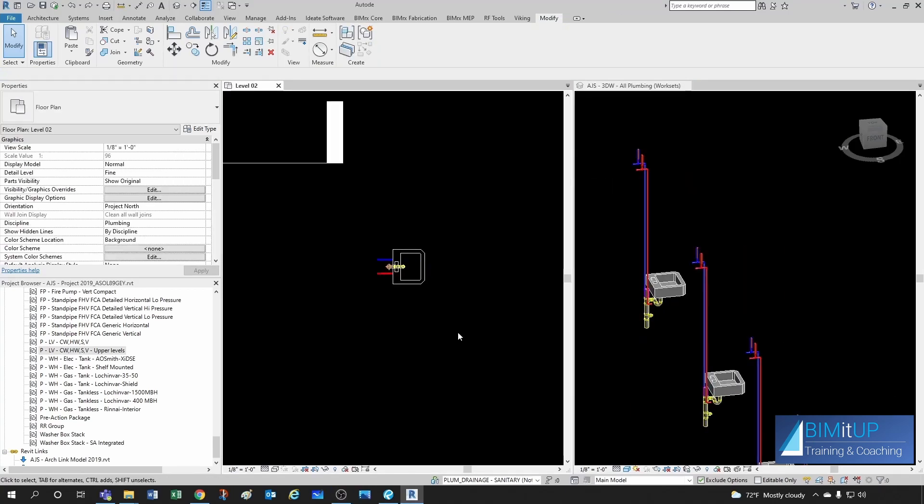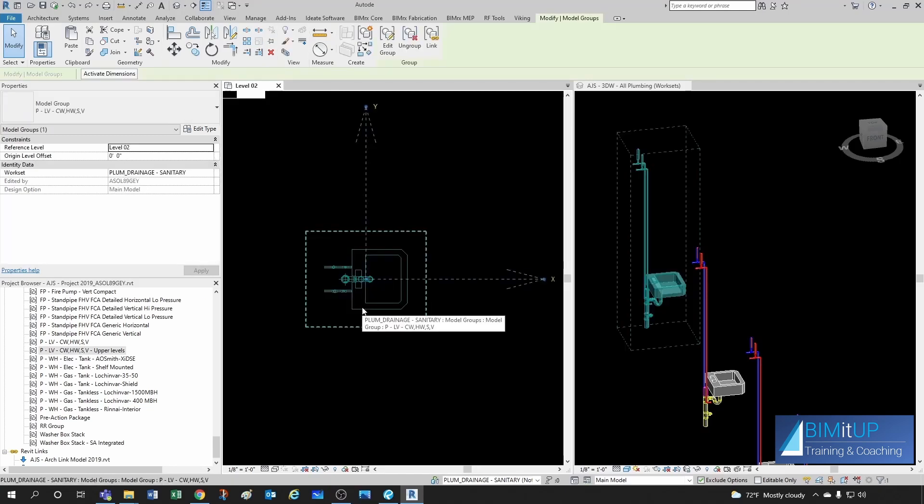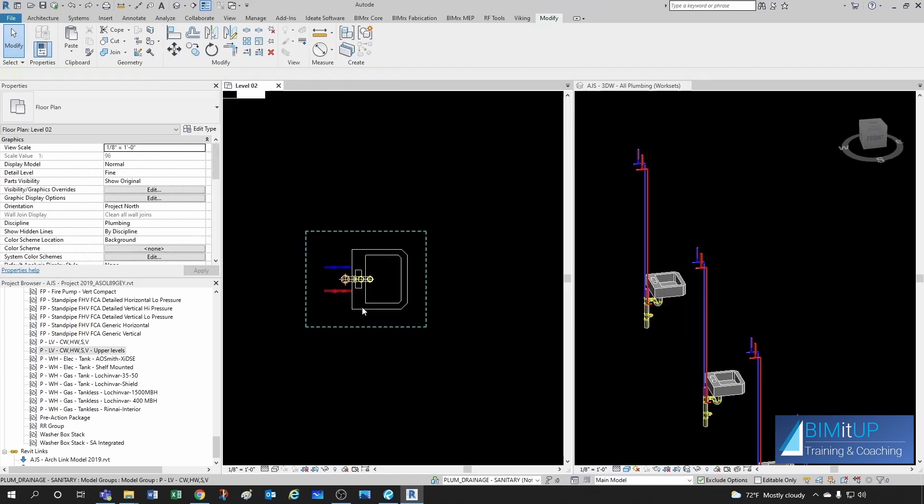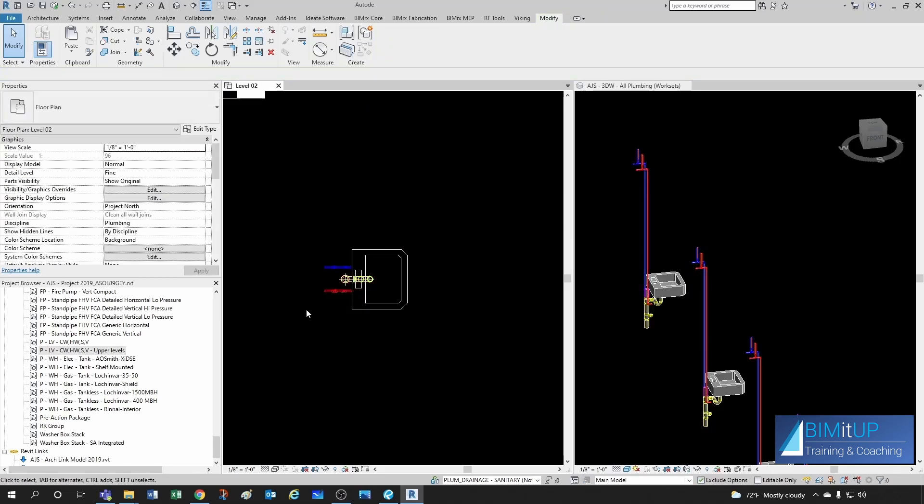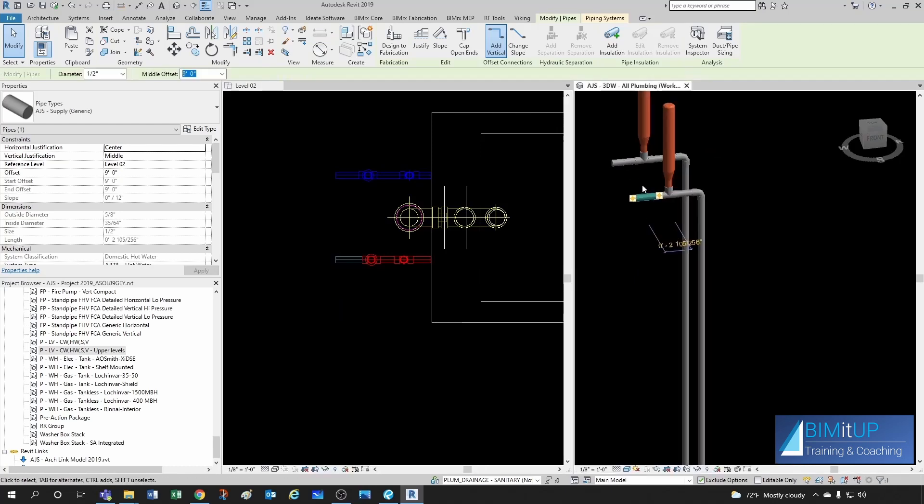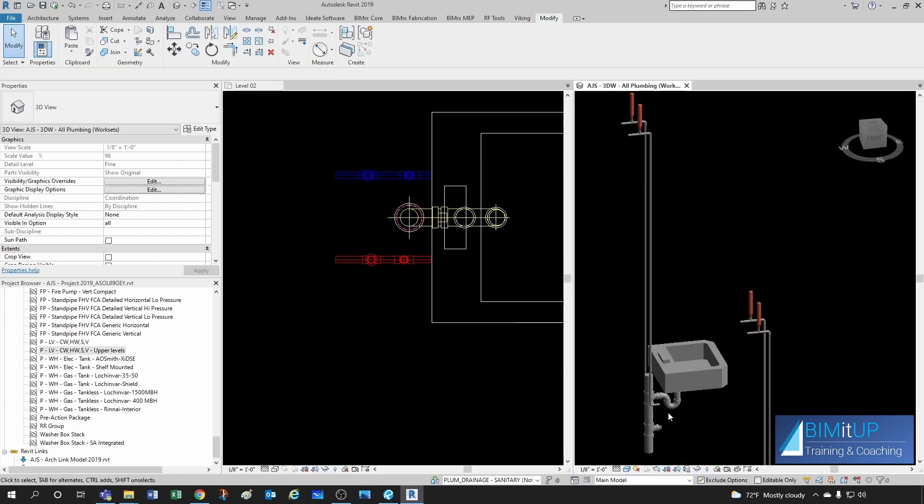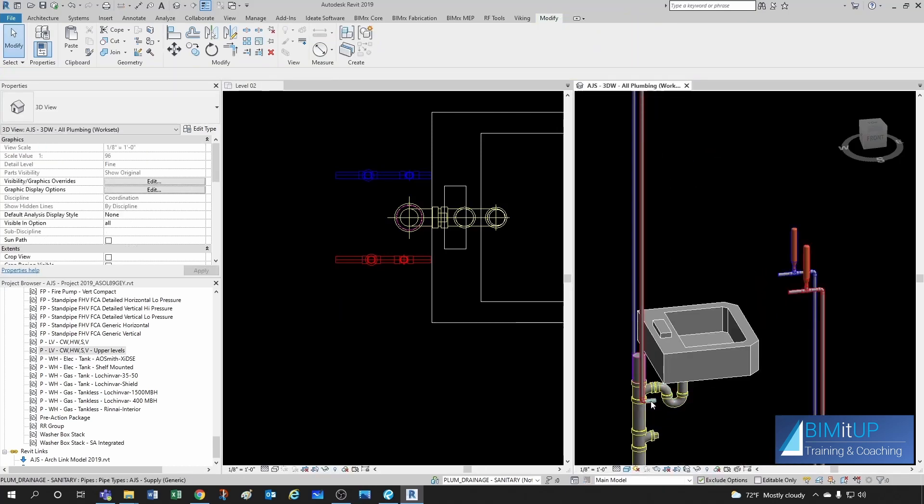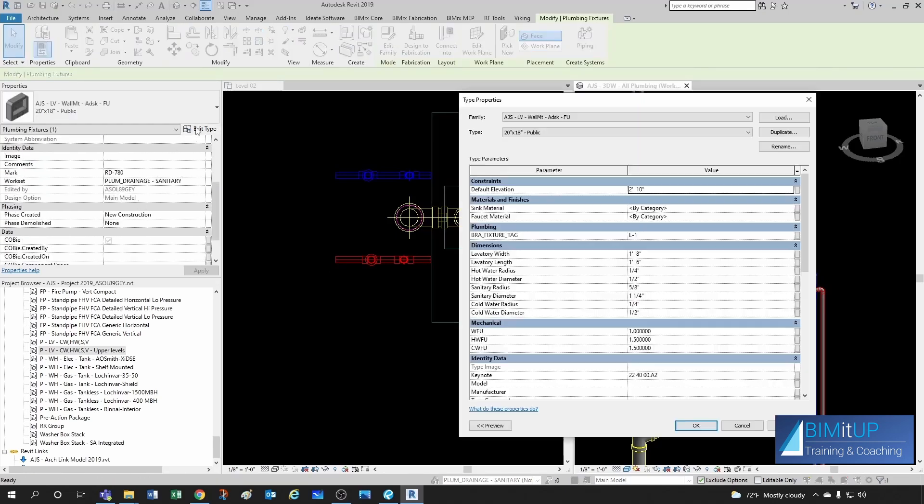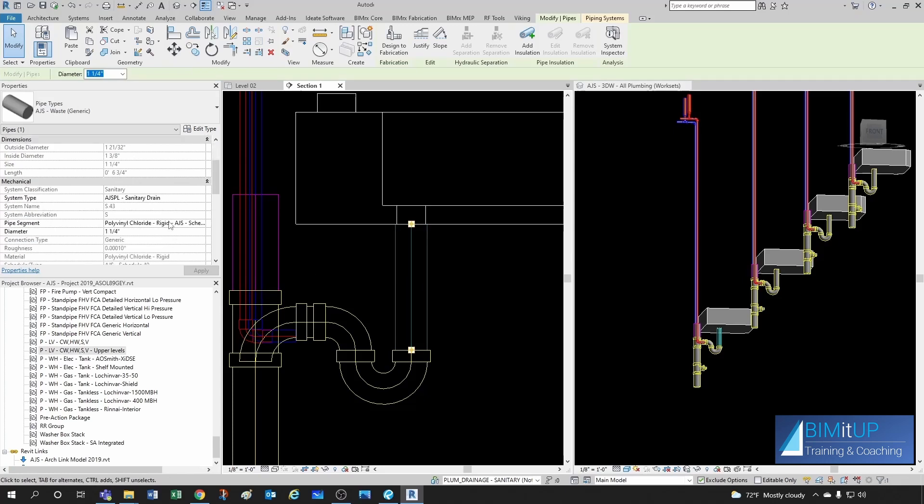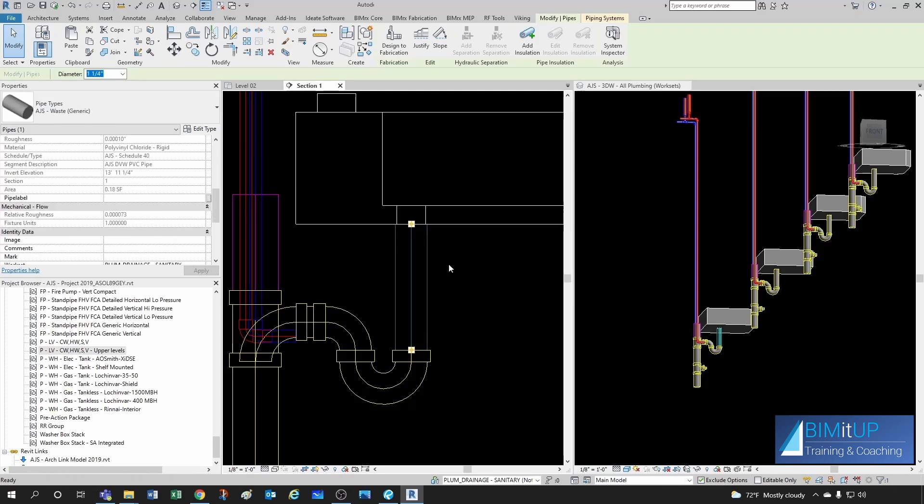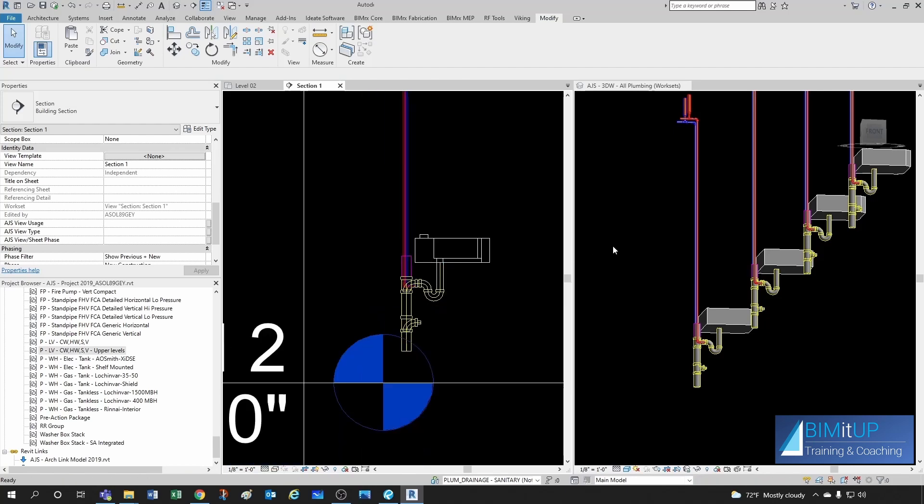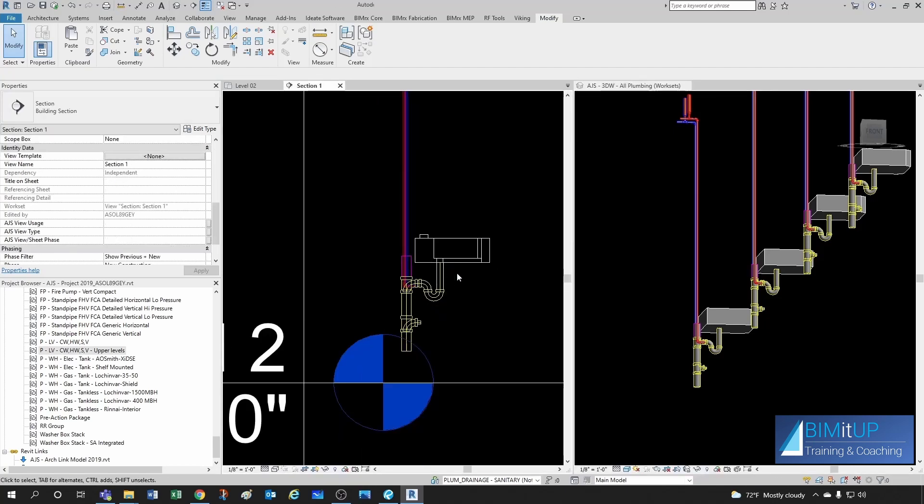Now one thing you want to be careful with groups is that, let me ungroup this. If I click on this pipe here, this is a hot water pipe that should be reading hot water fixture units out of this lavatory. If you click on this lavatory and you go to edit type, you'll see that it has for hot water fixture units, it has 1.5. And now let's see, we get a reading. There you go. One drainage fixture unit. So I have my reading in sanitary, cold water, and hot water.